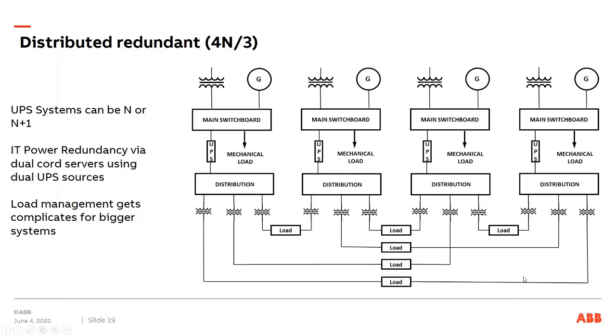In this case, you can load them up to 75% of nominal capacity of the UPS. And if one UPS fails, say UPS 3 fails, the load it's connected to will lose power from that side, but then it will get power from the backup, the other UPSs, 1, 2, and 4. They will now just go to 100% load. So it works.